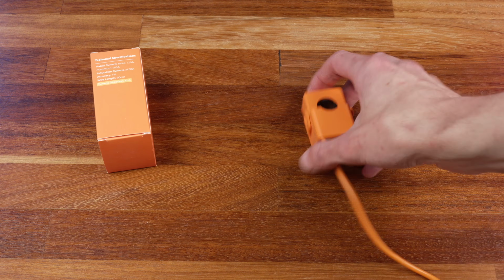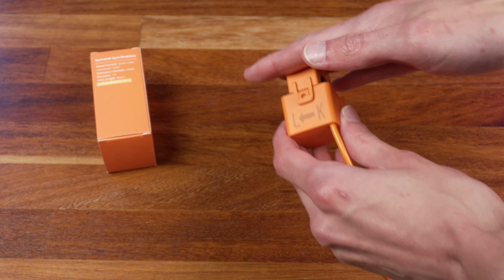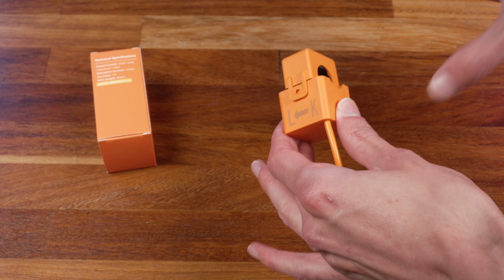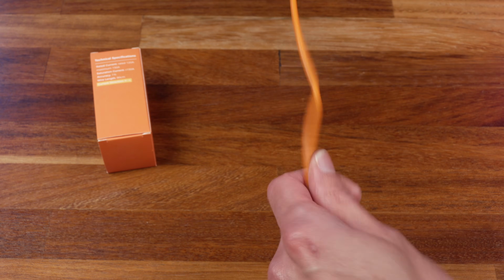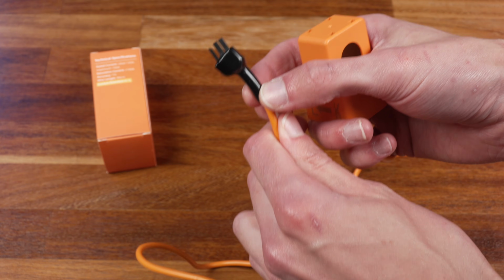Each of these CTs is rated up to 120 amps, as you can see on the box, and they're what is known as split core, which means you can open them up using this clip here and clip them around the wire without needing to disconnect anything. Then each CT has a nice long cable attached, really long, and then has connectors on the end, these little plugs, that'll plug into the energy monitor itself.